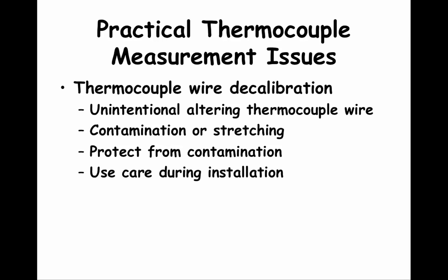Another thermocouple measurement issue can be caused by thermocouple wire decalibration. Wire decalibration occurs when thermocouple wire is unintentionally altered in some way. Wires can be altered by stretching, which makes the wires thinner. Wires can also be contaminated if the wires go through a corrosive or contaminated environment. Thermocouple wire decalibration can be mitigated by protecting wires that go through a corrosive or contaminated space. The other key thing to do is use care when installing thermocouple wires. This concept applies to other signal wires as well — be careful when installing them and protect them in corrosive or contaminated spaces.